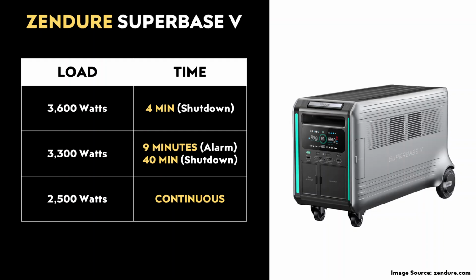However, beyond those numbers, you really can't run at that max continuously, or else this unit will protect itself and shut off the inverter. For instance, Zendure told me that if you run the unit at a max 3,600 watt load for around 4 minutes, the inverter will turn itself off to safeguard against overheating. In addition, if you run this unit at around 3,300 watts output, an alarm will activate after 9 minutes, and the over-temperature feature will be triggered after around 40 minutes. However, if you keep that output at around 2,500 watts or under, you can run that continuously, of course, until you run out of energy.